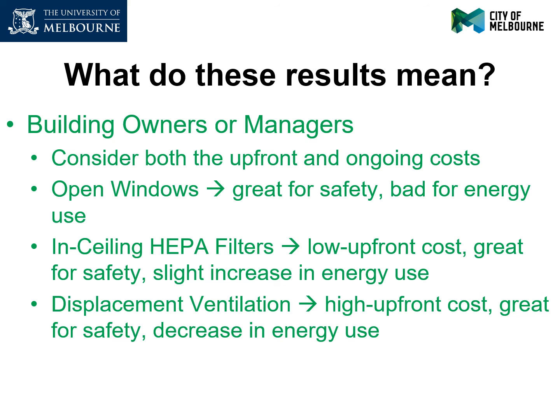This option was also able to greatly reduce the energy required by the chiller to cool the air, owing to the larger air supply temperature that could be used. As a result, this option was able to pay for its high upfront cost within 20 years.